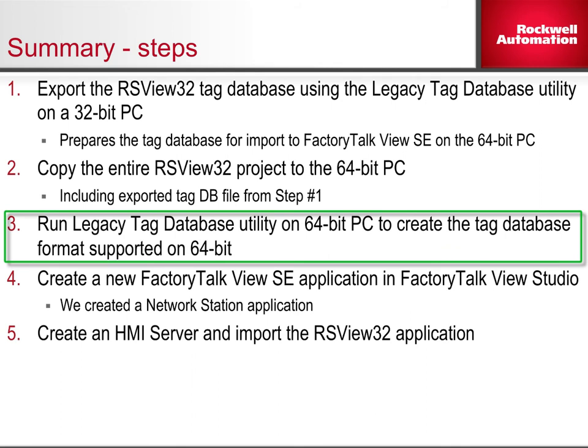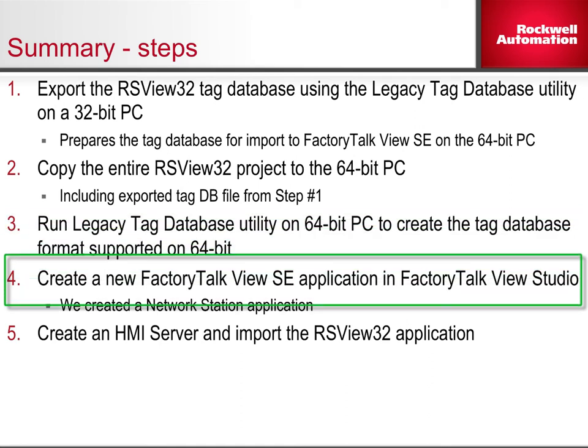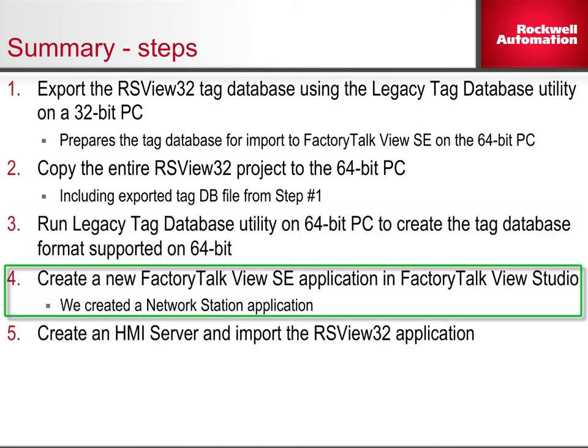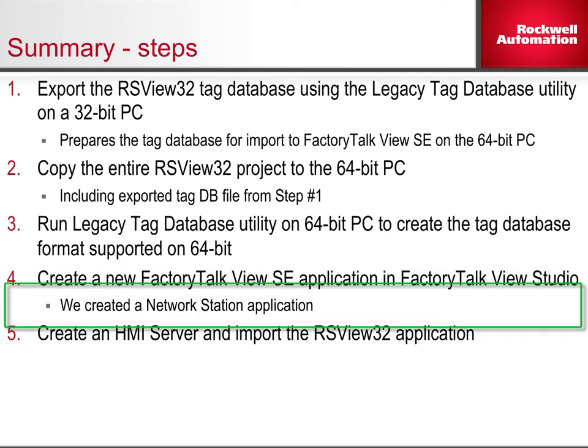Step 3: Run the Legacy Tag Database utility on the 64-bit PC to create the tag database format supported on 64-bit. Step 4: Create a new FactoryTalk View SE application in FactoryTalk View Studio. In this step, we created a Network Station application.